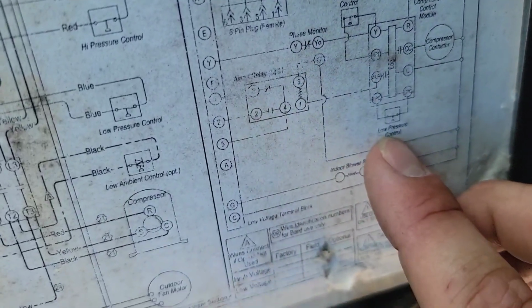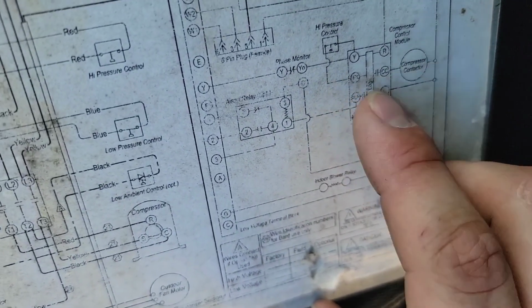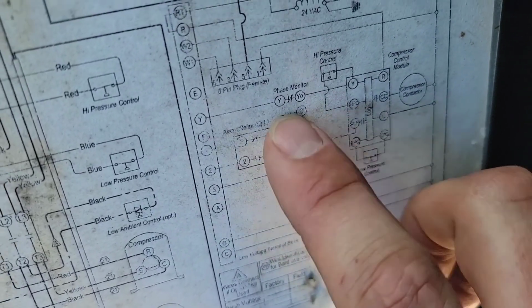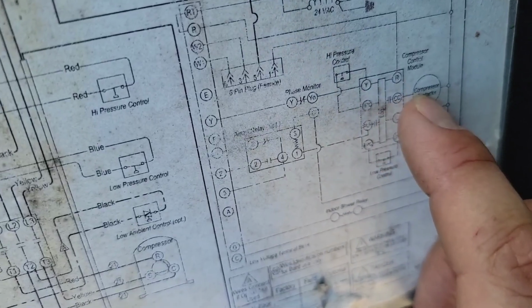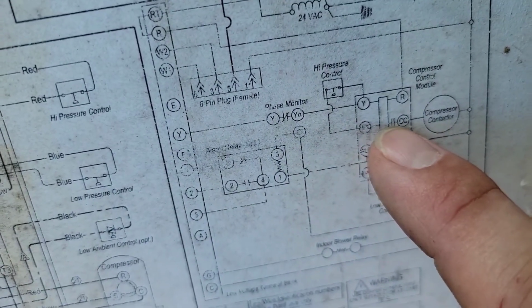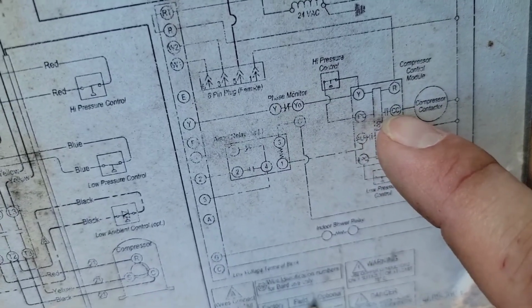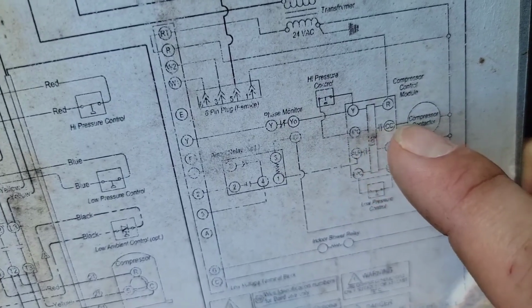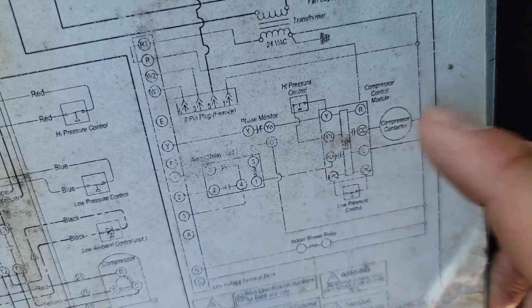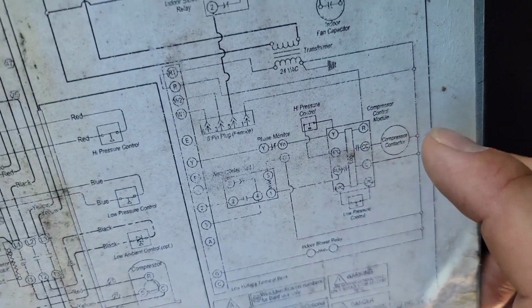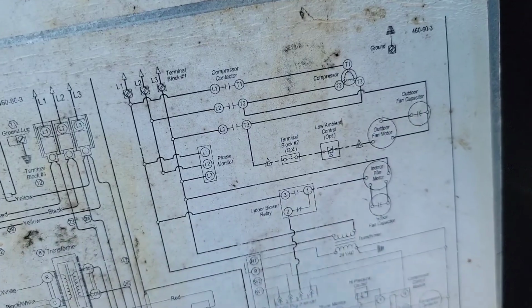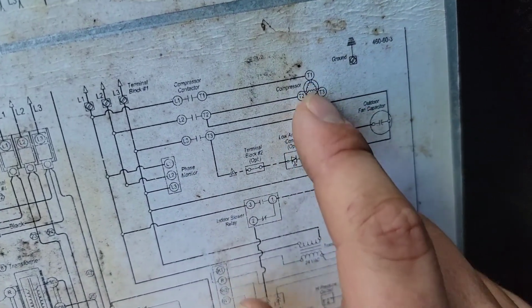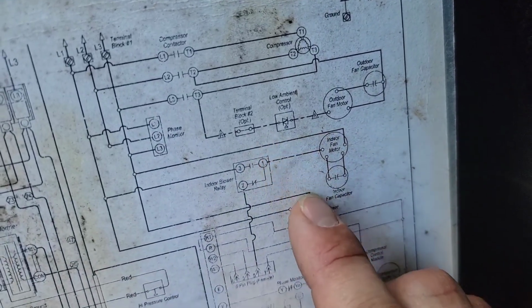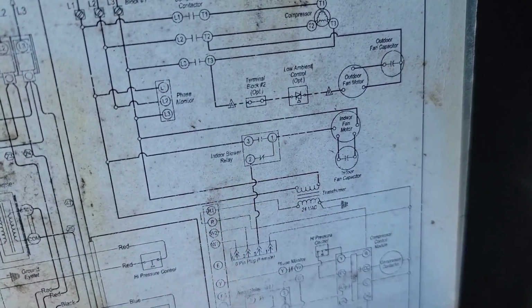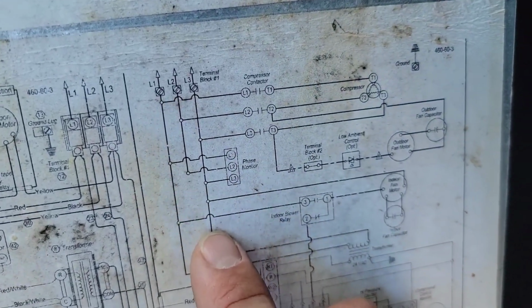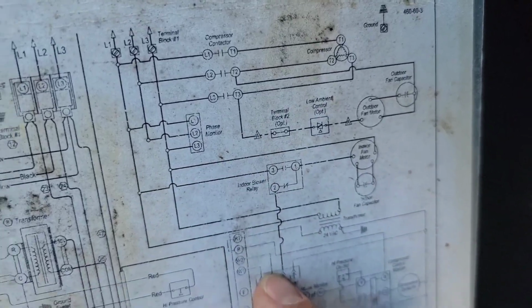If the high pressure control and the low pressure control are closed, then this little module or control should send power. And that Y should go through here, here, and then through here. See how there is a normally open set of contacts? That closes, and then you have your Y going through those contacts, or that power going through that contact to that coil of that contactor. And then boom, the compressor contactor should close the contacts, and then boom, we got power. And you can see right here, we got our indoor blower relay. We looked at that earlier. This is our 460 volt coming in. Phase monitor L1, L2, L3.